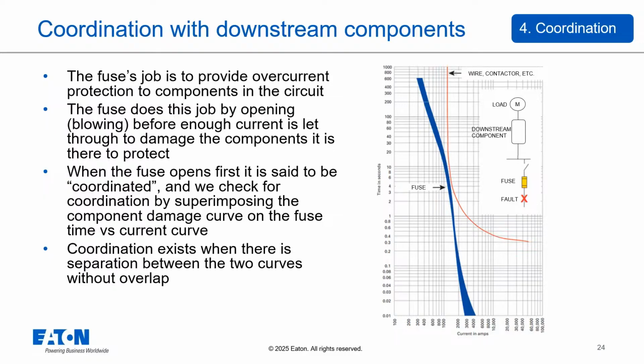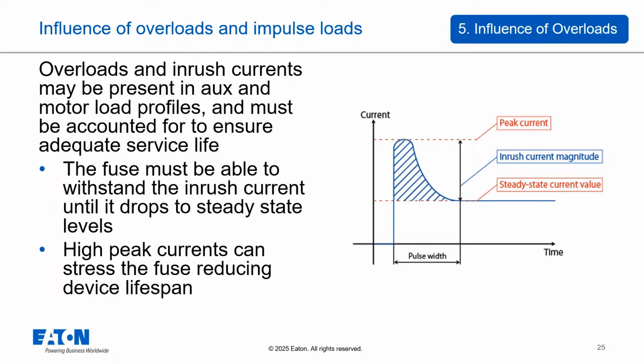Beyond just fault currents, we also need to consider the influence of overloads and impulse loads. Overloads, like sustained high power draw, or inrush currents, which are brief high current spikes when equipment turns on, can occur in aux loads and even motor drive systems. These loads must be accounted for to ensure the fuse lasts for its intended service life. The fuse needs to be tough enough to withstand these expected inrush currents without failing until the current settles back down to normal operating levels. However, very high peaks, even if brief, can stress the fuse element and reduce its overall lifespan.